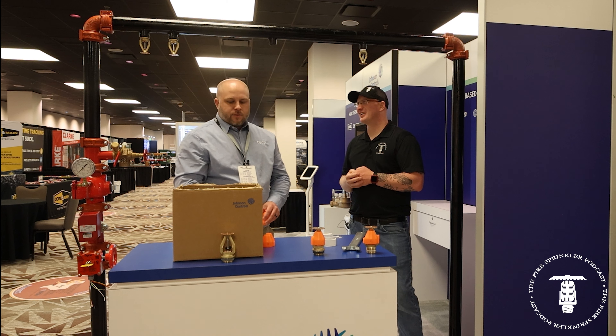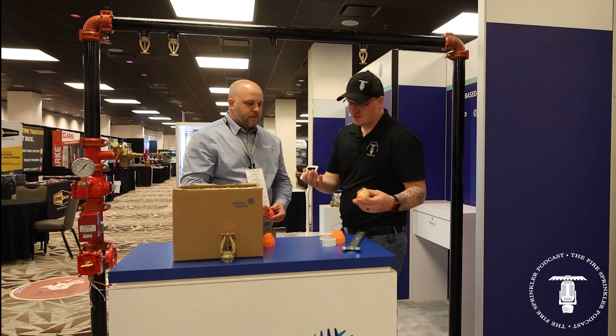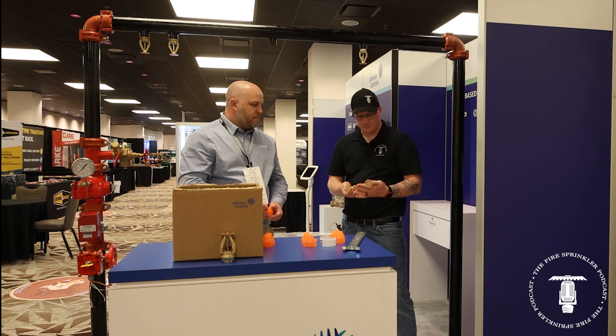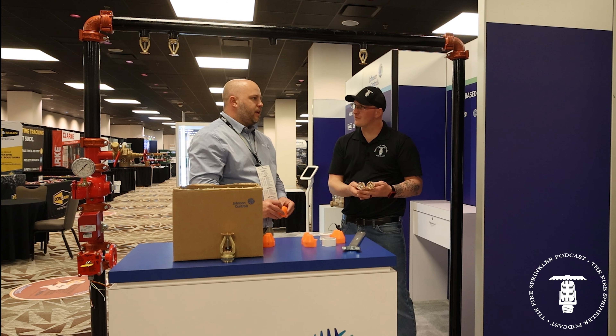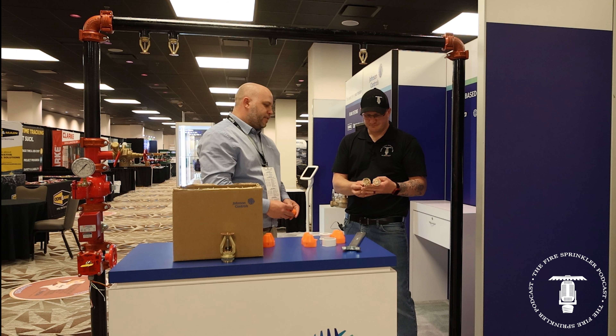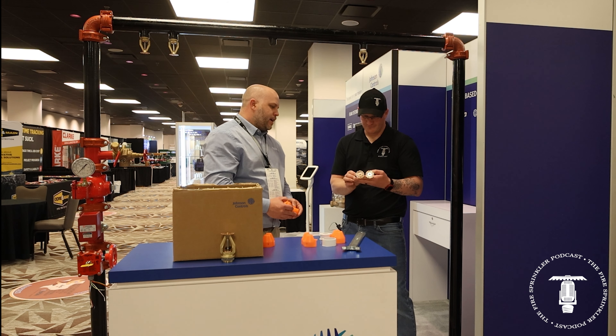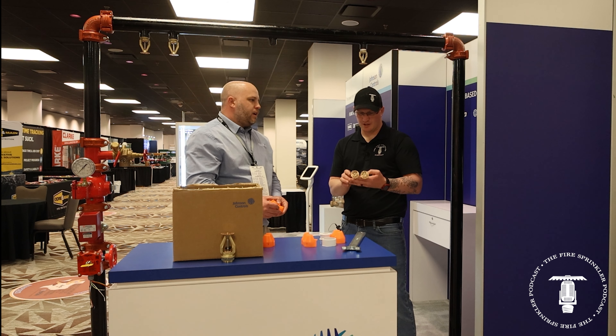The real benefit and true time savings is when you think about that hypothetical hydro at lunch. If I spend the other half of my day hunting down leaks, tightening them, and re-applying a hydro, I'm not hanging pipe on the next system. And you're never doing just a single system — you're always doing two or three at once. As far as the sprinkler design is concerned, it's exactly the same except for the connection type. That may not seem like a big deal, but I'm assuming you didn't have to go through the whole listing process again — you were able to submit all of your fire test data because you just changed the connection type.